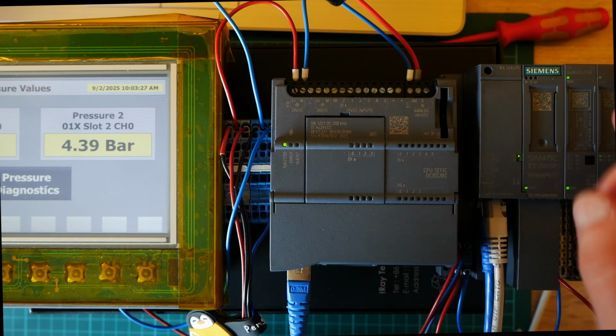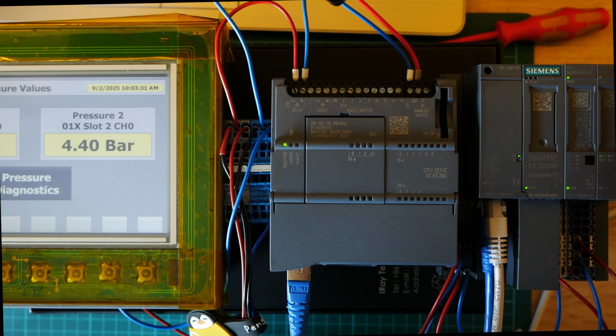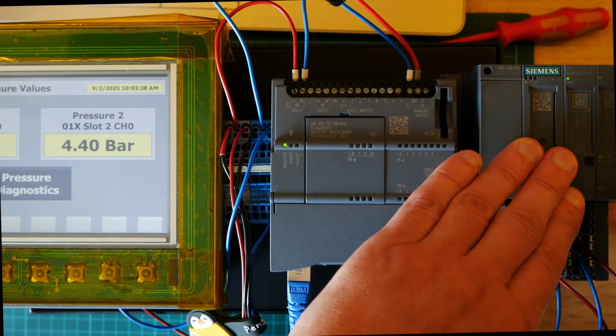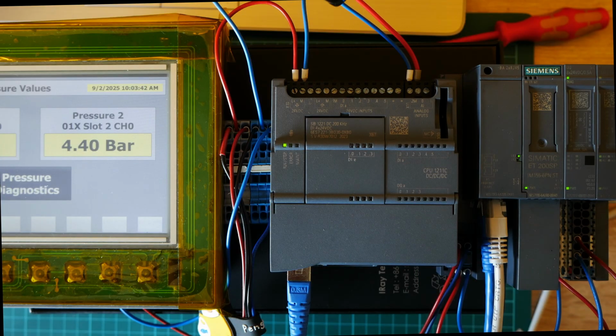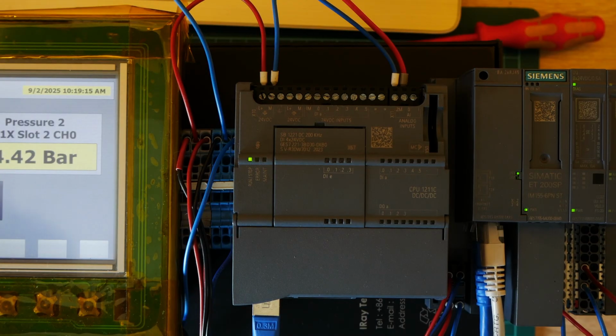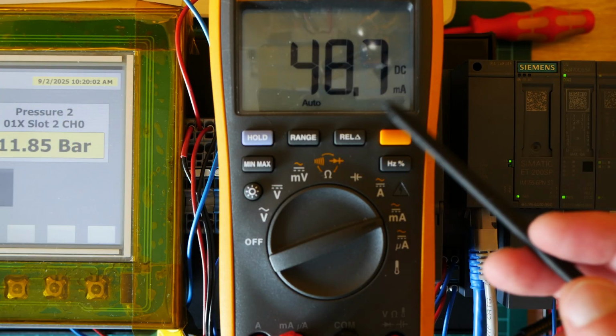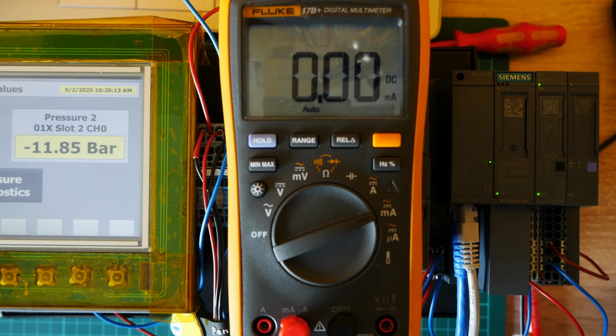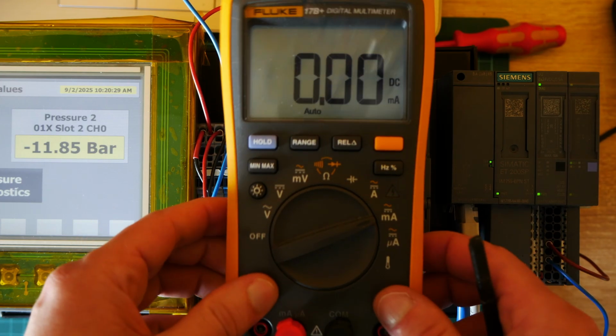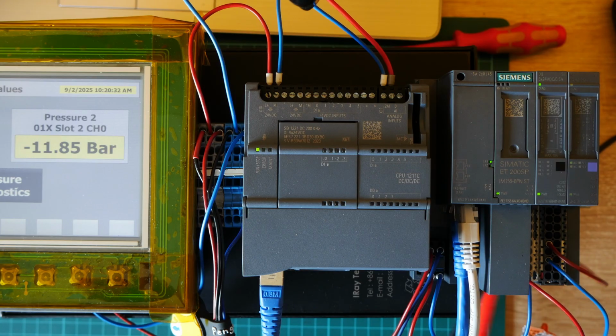So the electrician goes to the 0.1 electrical cabinet. He knows that something is going on with the analog input card. He presses it back in and that's it. Our process is working. So you can obviously use your multimeter in milliamperes. As you can see, yeah, it's not good. I'm shorting this analog module, but you can imagine you have a transducer, you can check. Okay, this input should be between 4 to 20 milliamperes and it's giving me 0 milliamperes. So it definitely is an issue with the transducer.